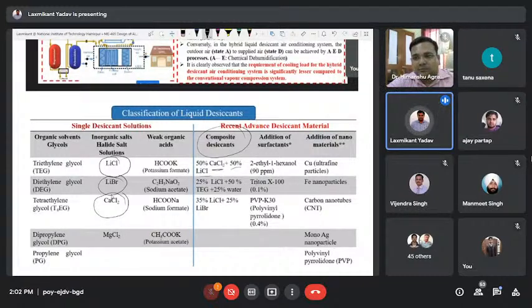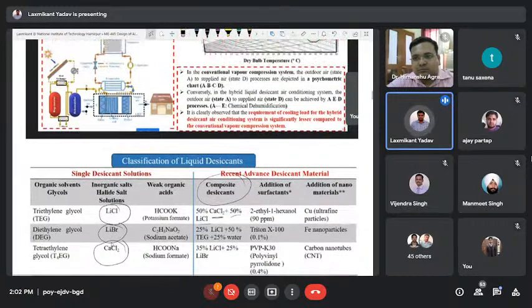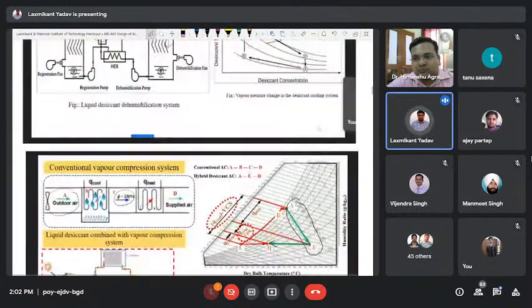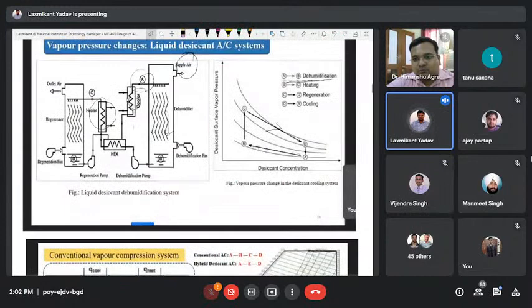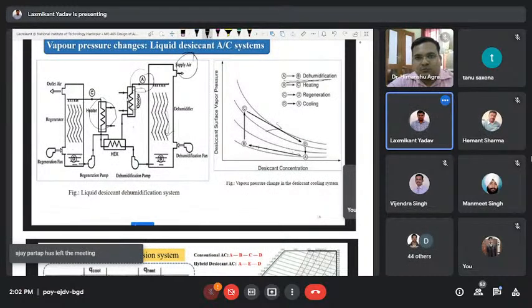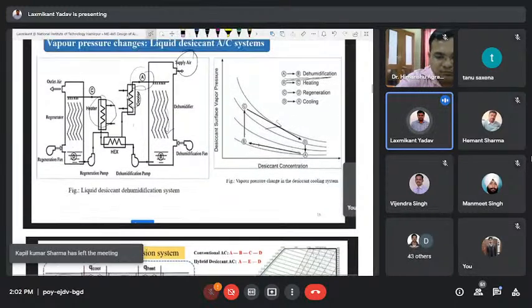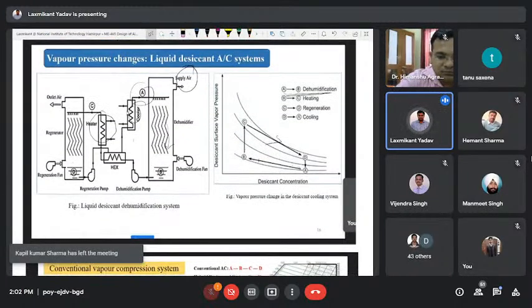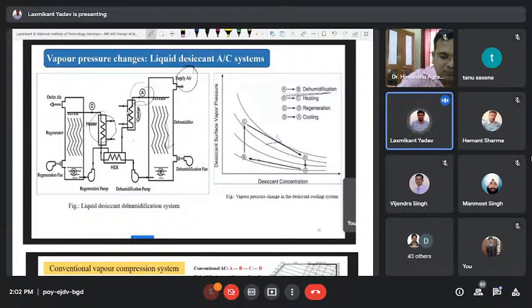But if you want to develop a setup of a liquid desiccant air conditioning system, then you require two chambers, an absorption chamber and a regeneration chamber, pumps, and a heat exchanger, but you can develop this system. However, the desiccant wheel is a simple, compact system. There is one wheel where dehumidification and regeneration continuously take place.